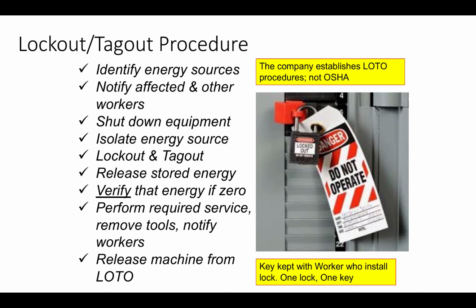The lockout tagout procedures are simple. The company establishes the lockout tagout procedure, not OSHA. The key is kept with the worker who installs the lock. One lock, one key. You don't want to have a chance of anyone coming and removing your lock on a locked out system. We need to identify energy sources. We need to notify affected and other workers. You shut down the equipment, you isolate the energy source, you lock out and tag out. You release any stored energy, that would be capacitors. You verify that the energy is zero. You perform the required service, remove tools, notify all other workers. You release the machine from lockout tagout and re-energize. Again, tag, lock, one key.